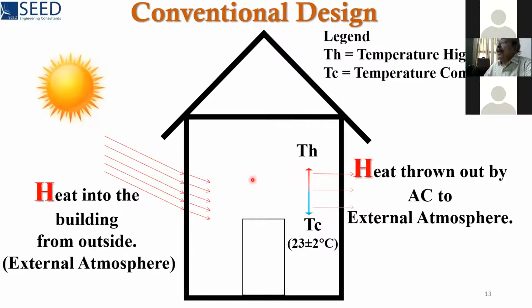See, this is a funny procedure. This is a paradoxical concept, a design not in the proper way, because we are first admitting heat energy to come into the building, and thereafter we use an air conditioner, spending money from our pocket, and throw a portion of that heat energy to the same place from where it came in. It would have been far better had we prevented heat gain into the building at the first stage itself, by preventing it from coming into the room. So that should be our approach. How will we do that?